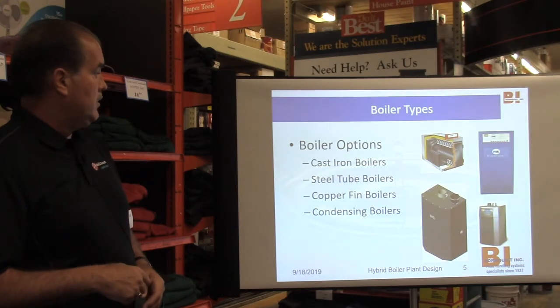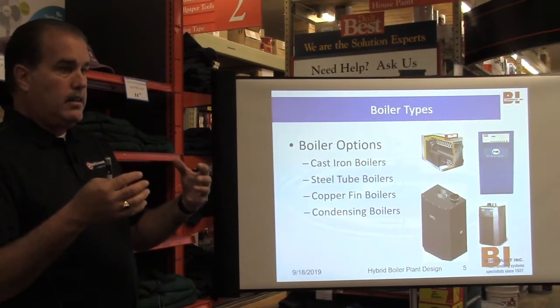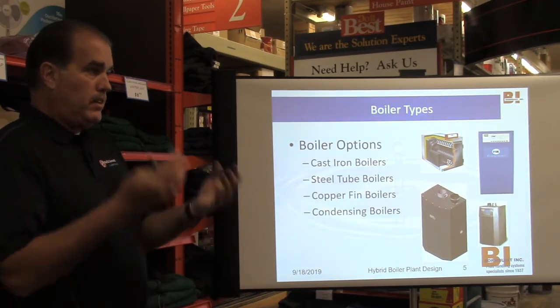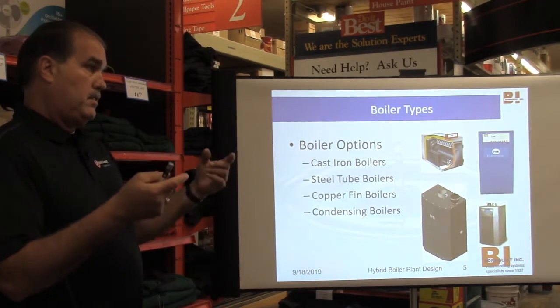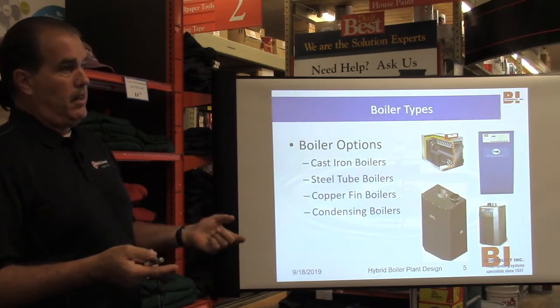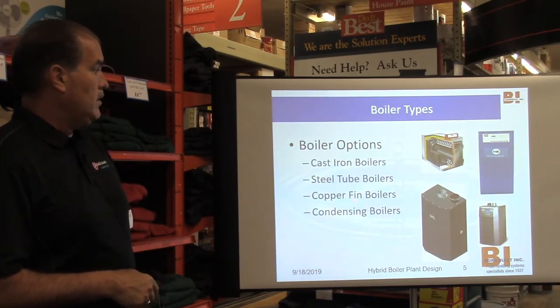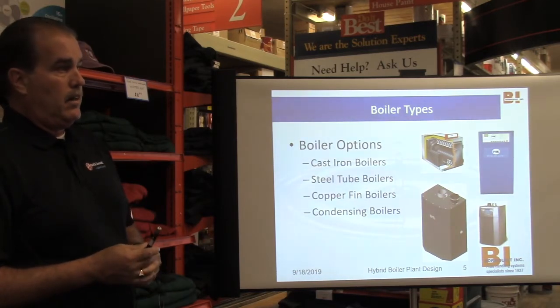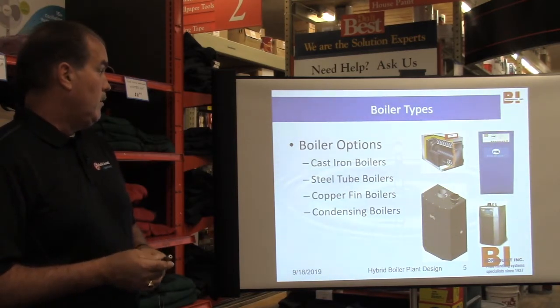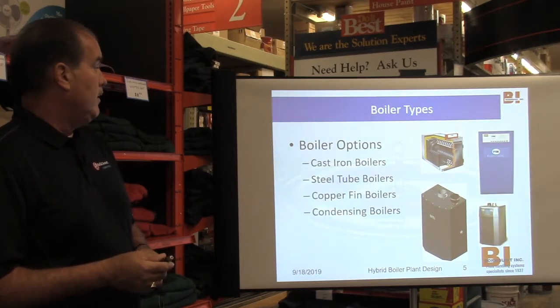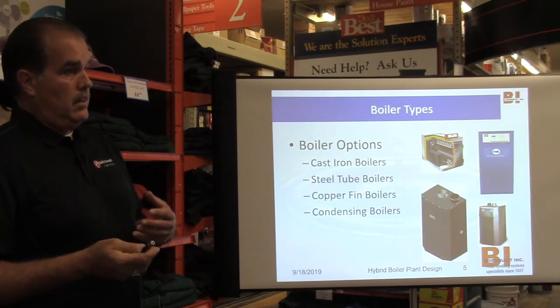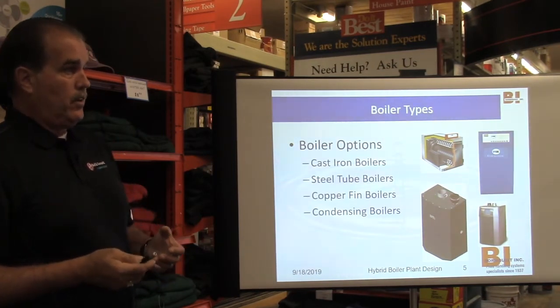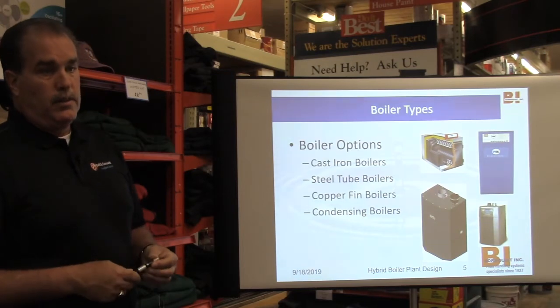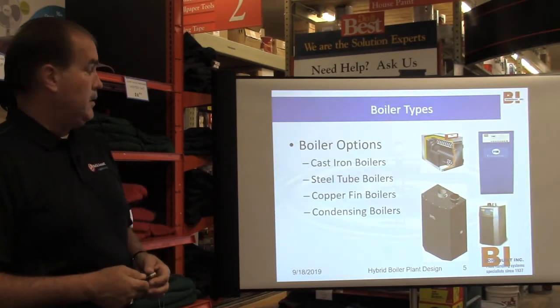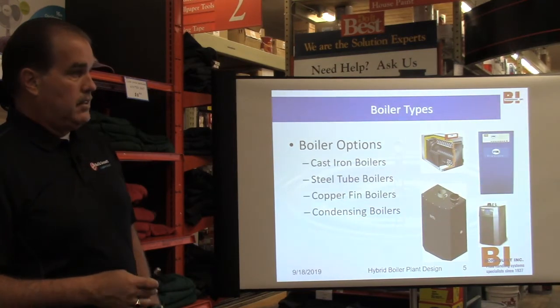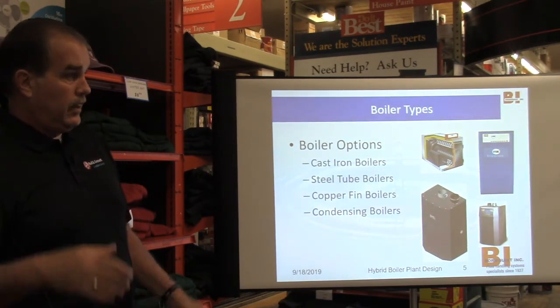There's steel tube boilers, there's copper fin boilers. These are just the way they're designed. Rather than being cast iron, these are actually steel tubes, and they run the heat past the steel tubes. Sometimes the water's on the inside, sometimes the water's on the outside, depending on whether it's water tube or fire tube. Copper boilers are often used in water heating, domestic water, and they're pretty efficient. They heat the water really fast, but you have to watch your flow, because they require a lot of flow. If you don't get the proper water flowing through it, you can overheat the copper and actually melt it.